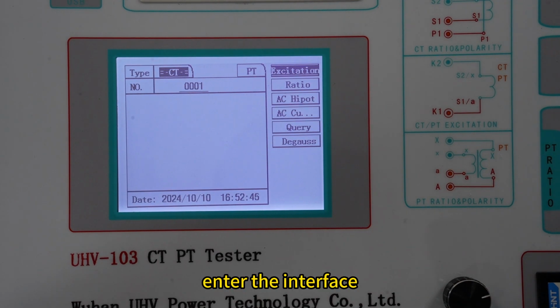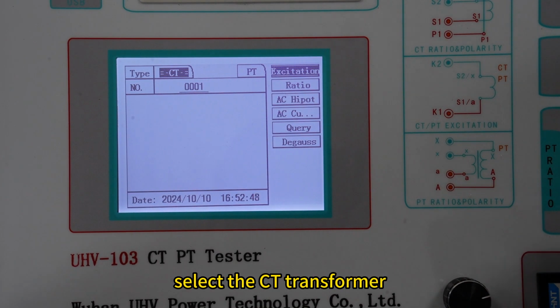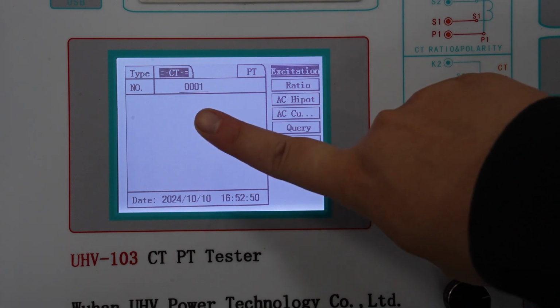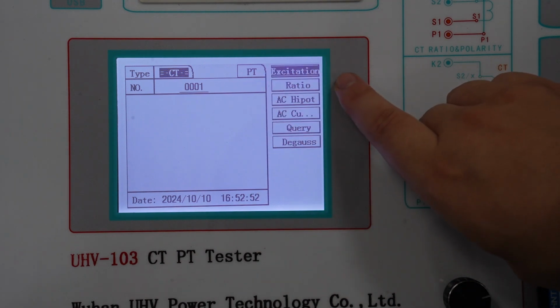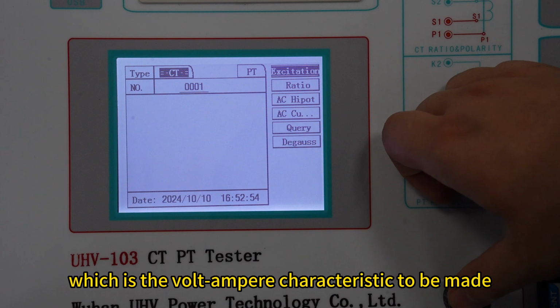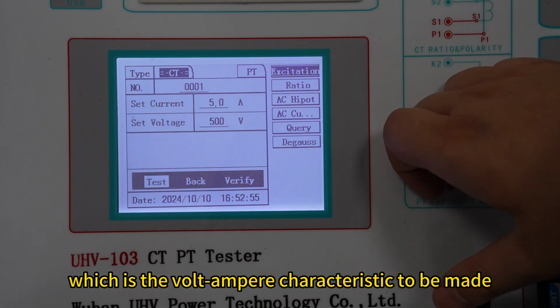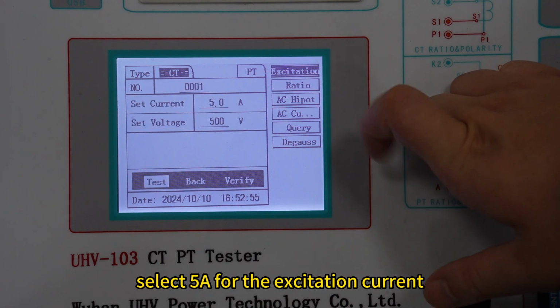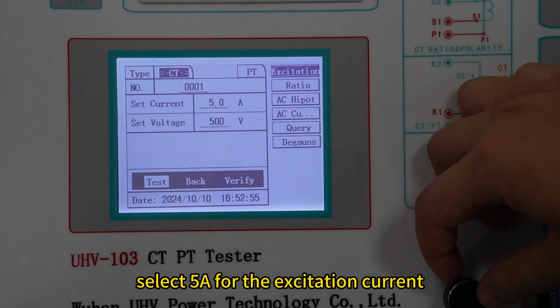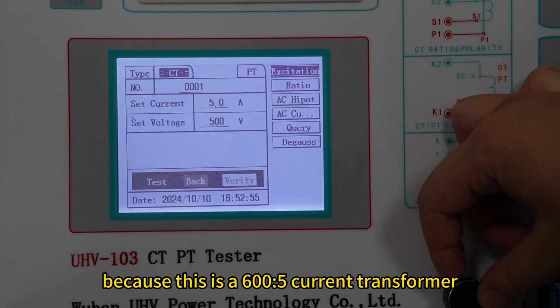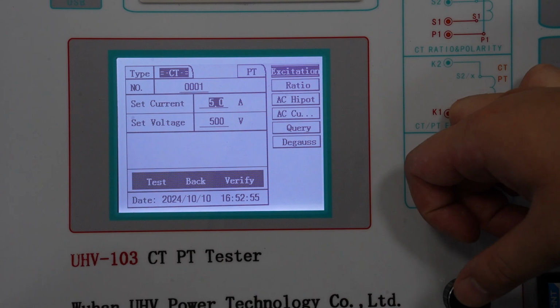Enter the interface. Select the CT transformer. Select excitation, which is the volt-ampere characteristic to be made. Select 5 amperes for the excitation current, because this is a 600 to 5 current transformer.